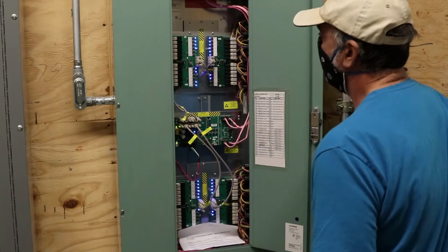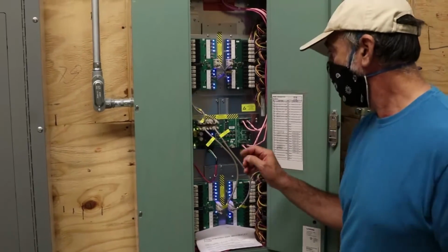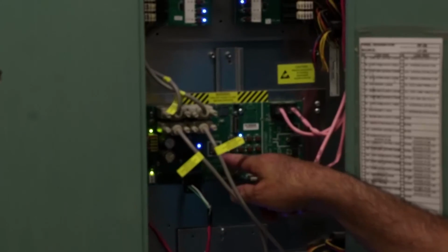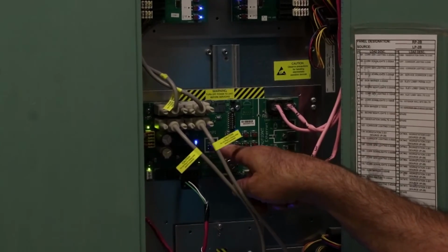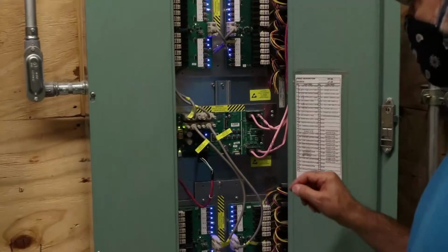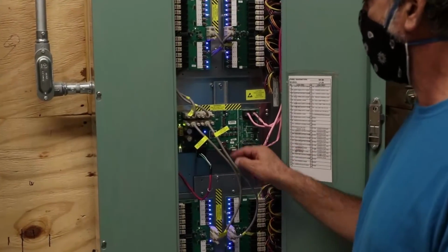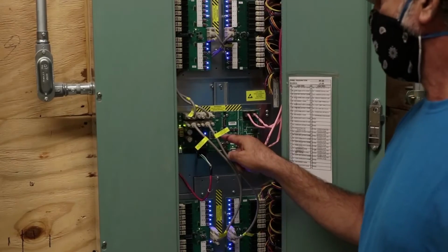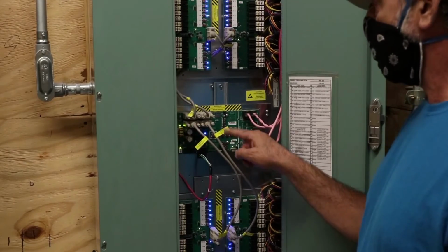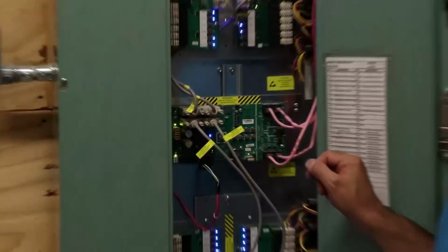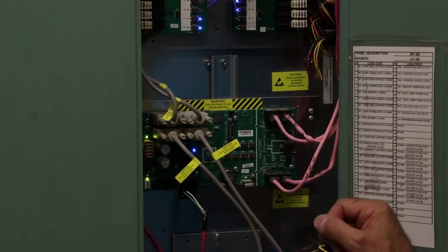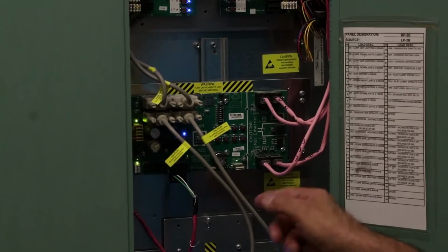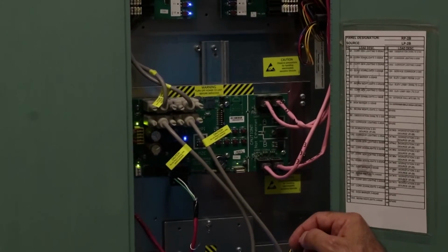So under normal conditions, looking at the main processor, this light is the main one right here. This little red light that's flashing, it actually says config. The technicians refer to that as a heartbeat, so it's supposed to be flashing. If it's solid, steady red, that means there is something wrong. Could be a bad board, could be a short in one of these cables, but there's something wrong. It should always be blinking.